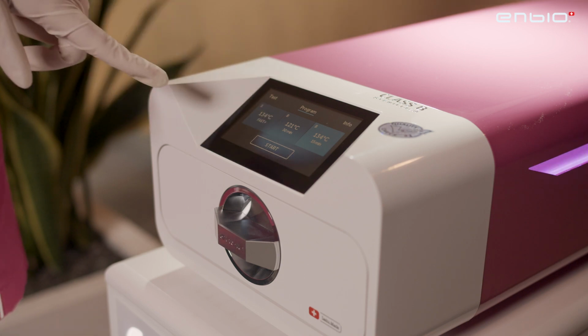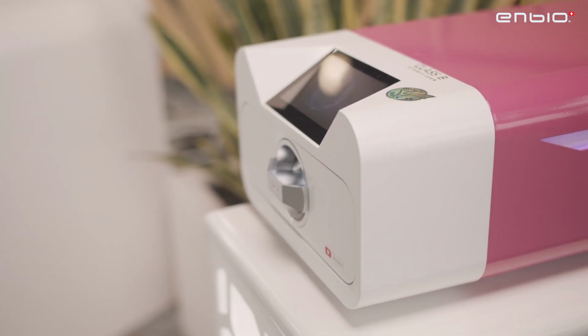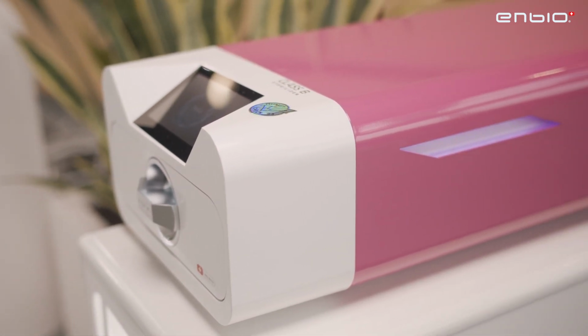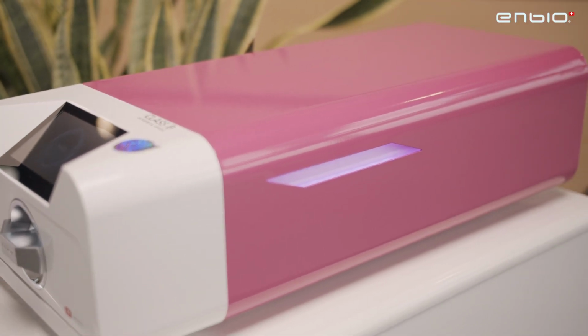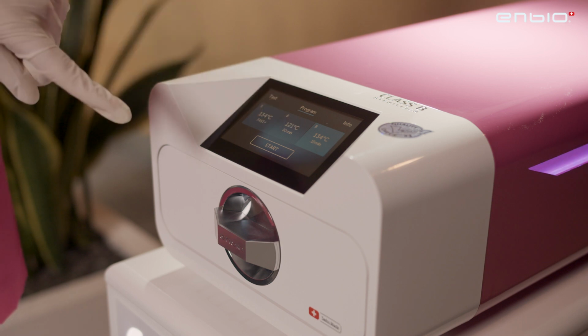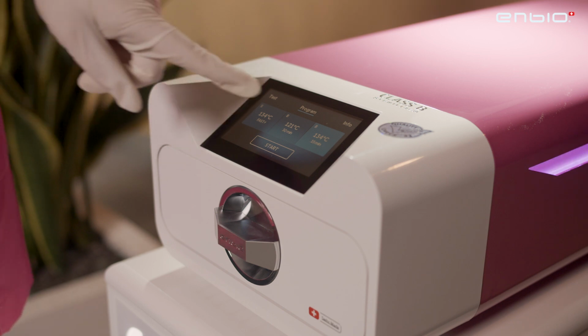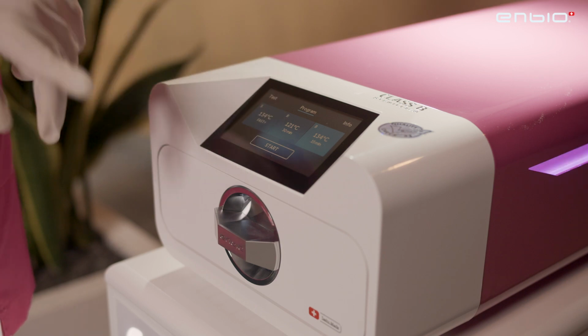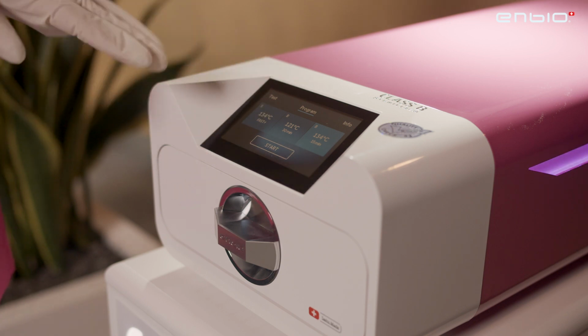The second program sterilizes the tools at 121 Celsius degrees and during 30 minutes, and it is a Class B sterilization program that we can use with the tools that are more sensitive to very high temperatures. So for instance, if we are using tools that have a silicone part, it is recommended to use this program here. And the last program, it is still a Class B, and it sterilizes the tools at 134 Celsius degrees during 15 minutes. And this can sterilize all kinds of tools, wrapped and unwrapped, porous and non-porous. So this is the one recommended if you don't use sensitive tools, for instance.